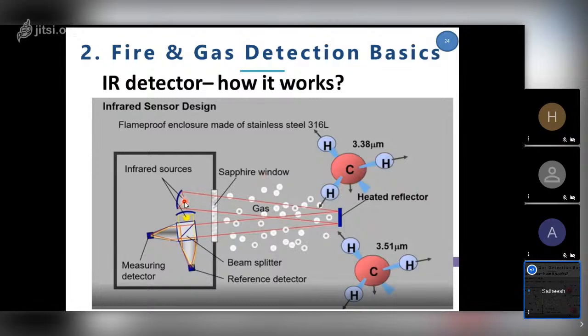To start with, there are two IR lamps, infrared lamps. We call them sources. The red one is the actual measuring infrared, and the yellow one is the reference. As I told you before, a reference comes in all the equipment to compensate for external effects. For example, the infrared beam is going out and coming back.